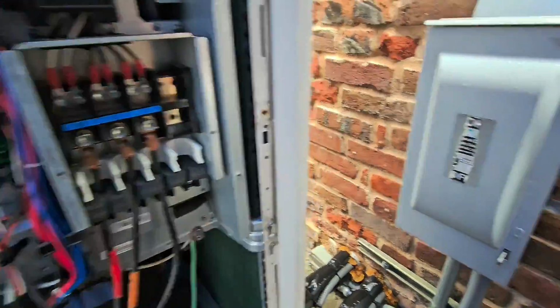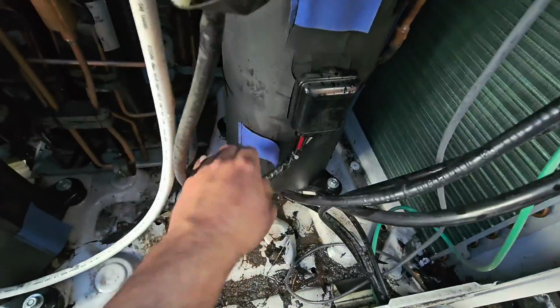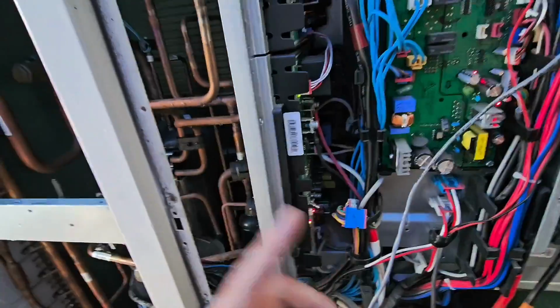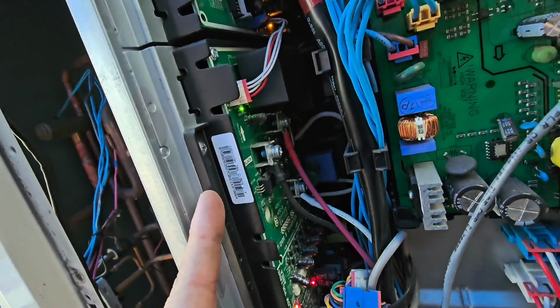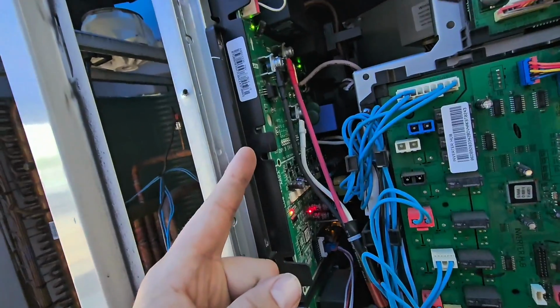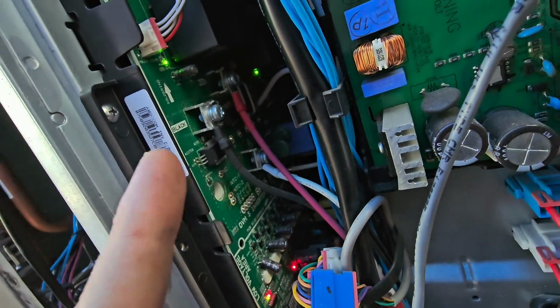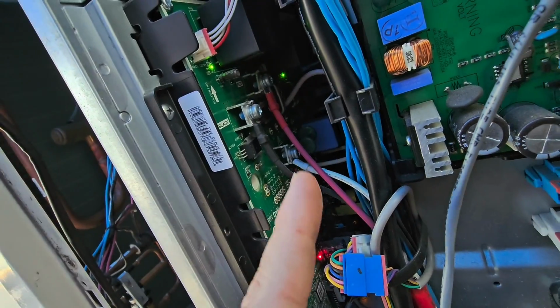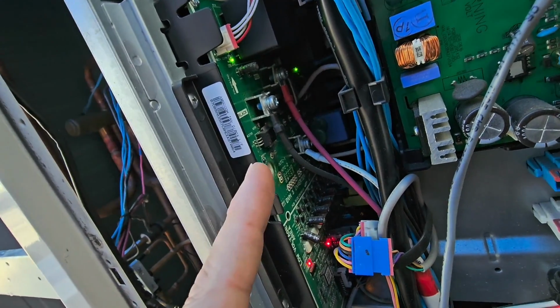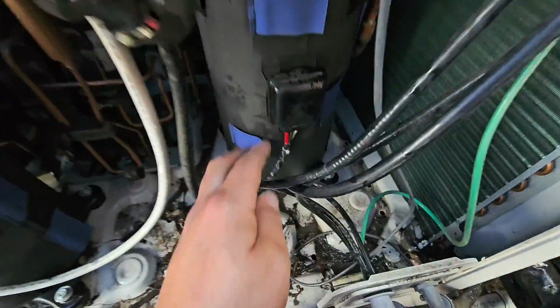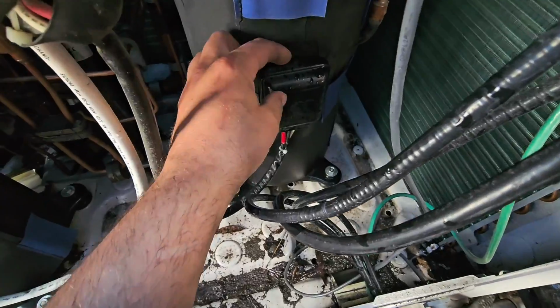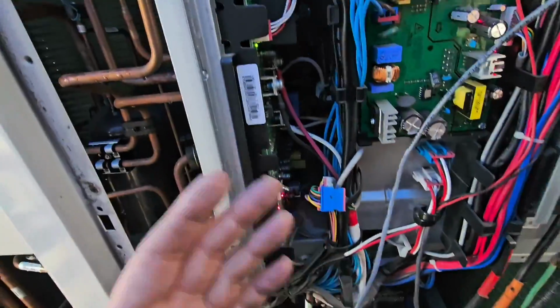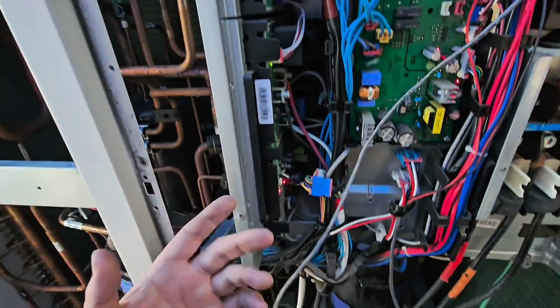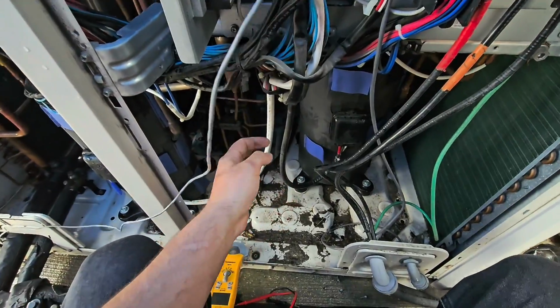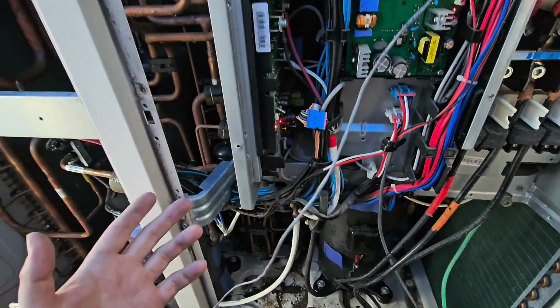Now, once I verify that we have the correct power, then I shut the disconnect off. And then I check the wiring from each compressor to each inverter board. I've got this inverter board and this inverter board. So we got 2 inverter boards, and the terminals that are black, red, and white, which have the white, black, and red wire, those are the wires that come from the inverter board to each compressor. There's one compressor, there's another compressor. So you take and you disconnect the power, and then you take this cover off, and then you check each terminal. Then you check the wires going all the way up and make sure that you have good connections and that there's nothing wrong with the wiring. That is the second step.